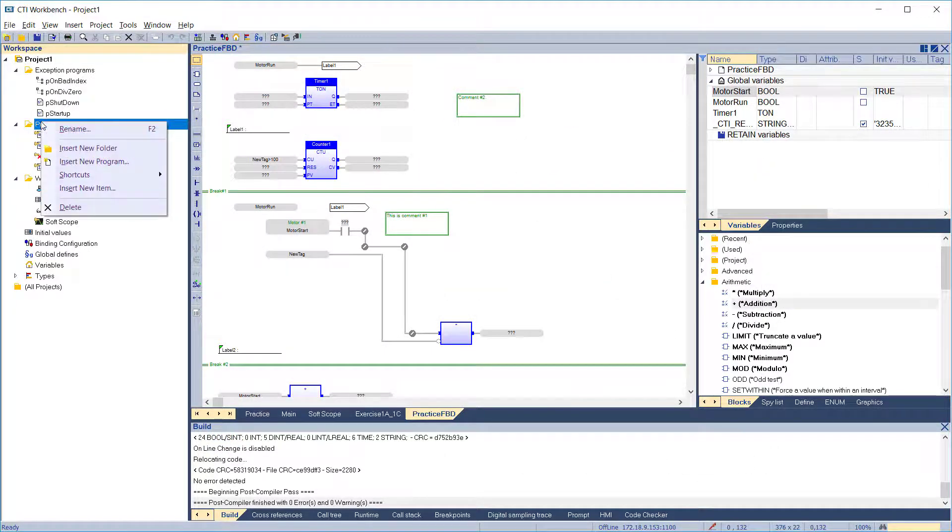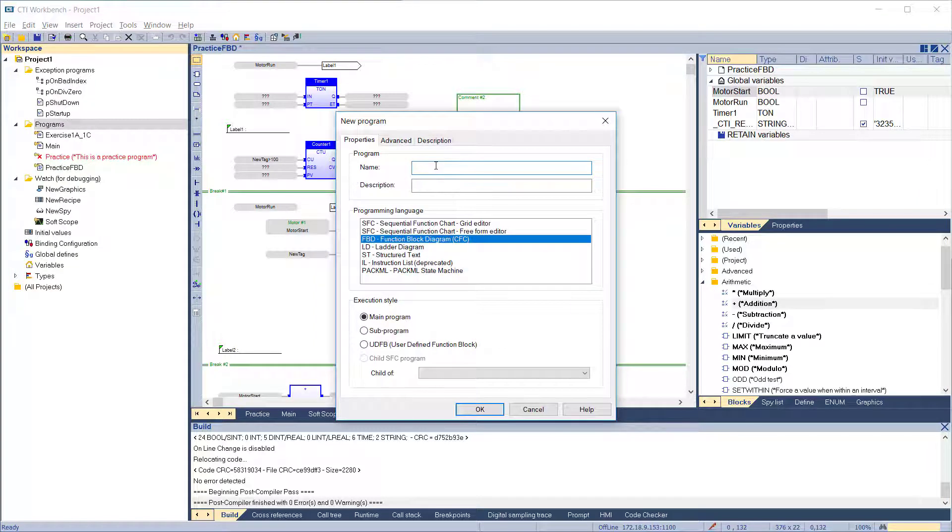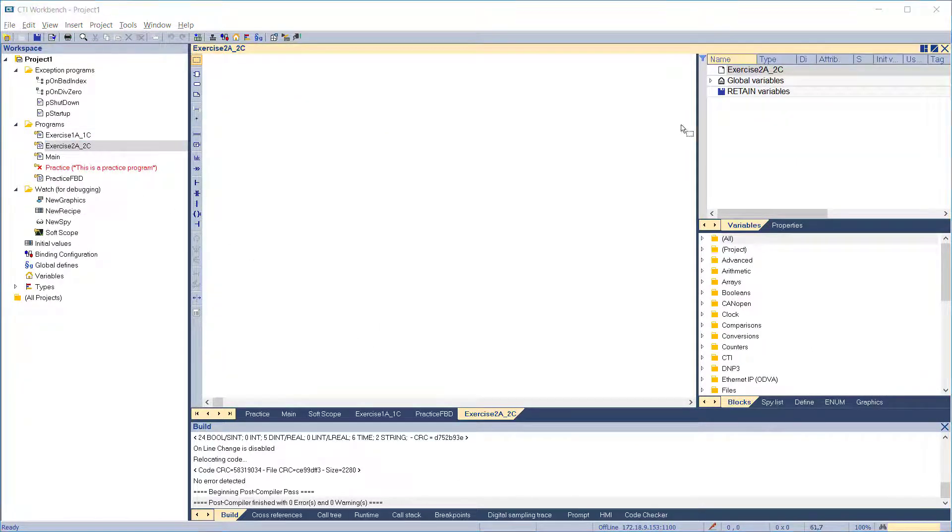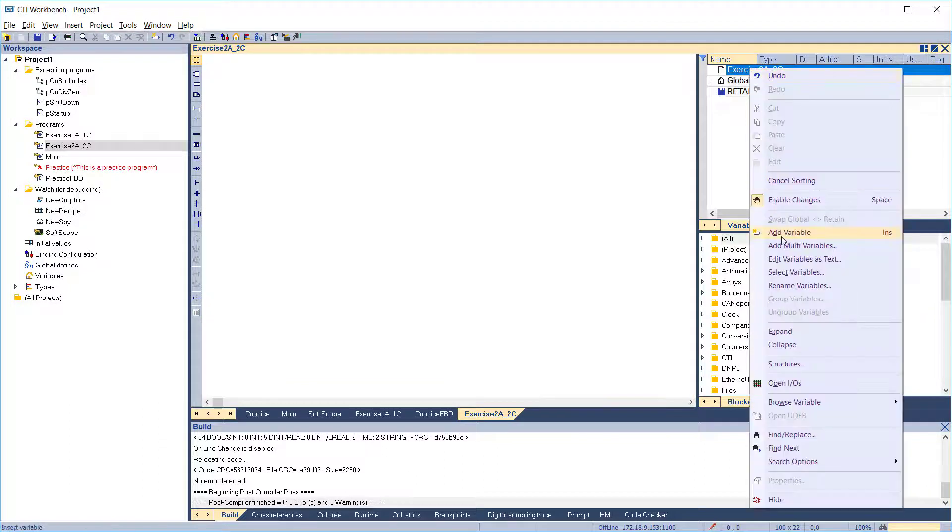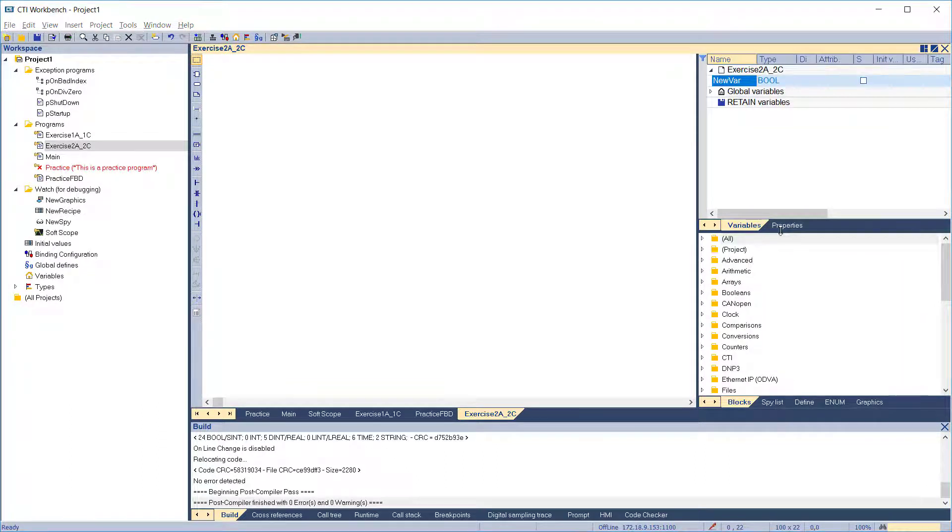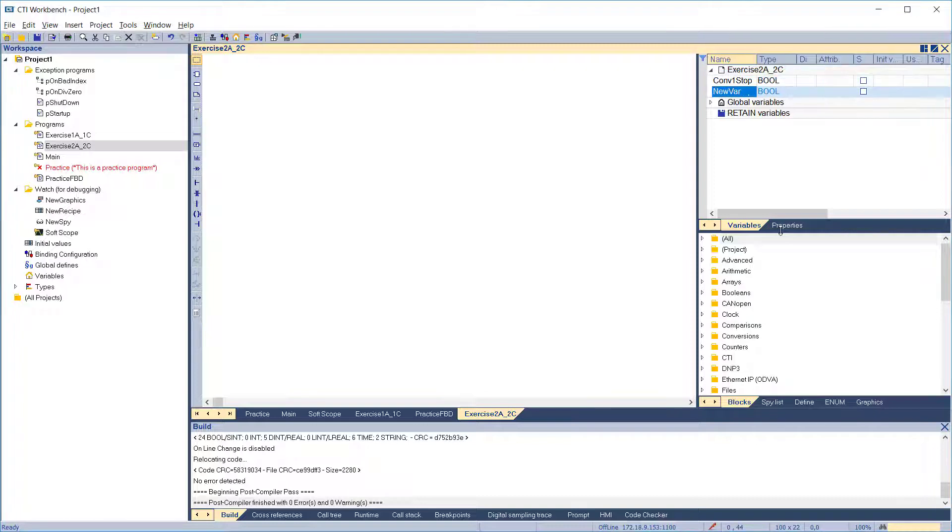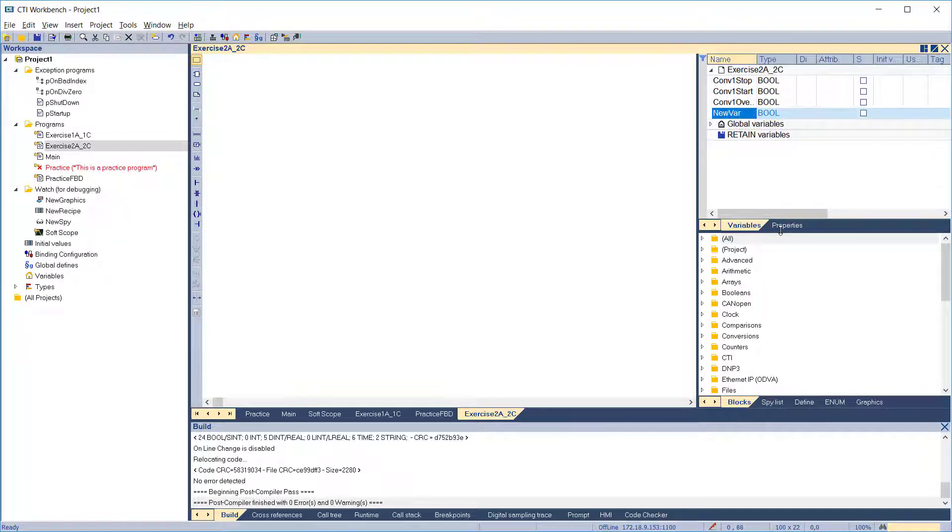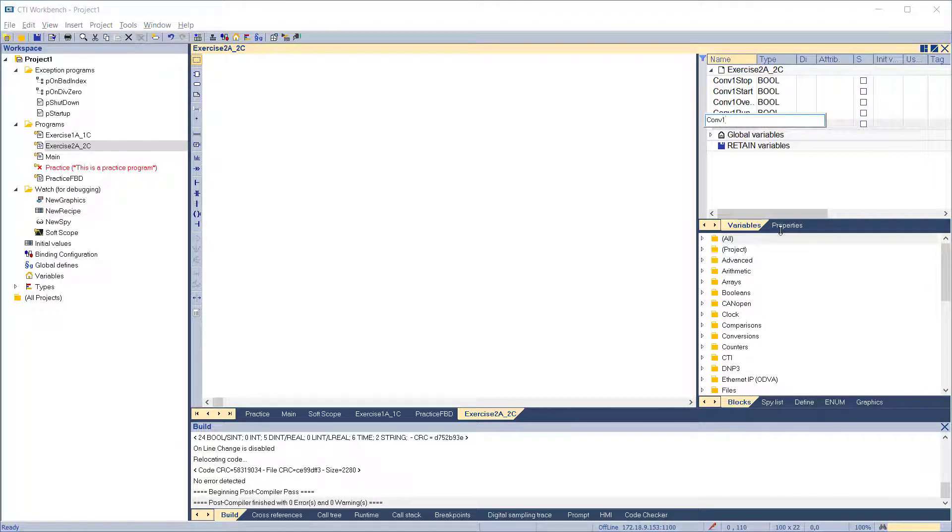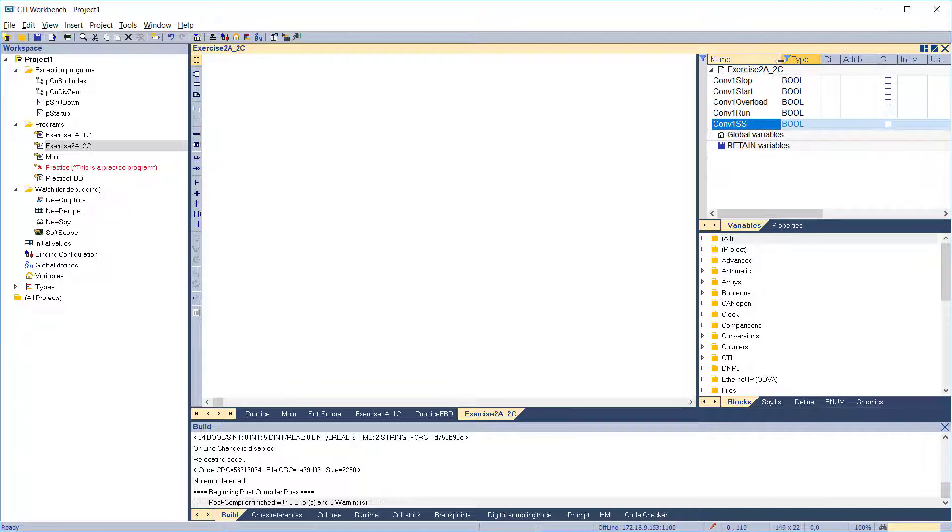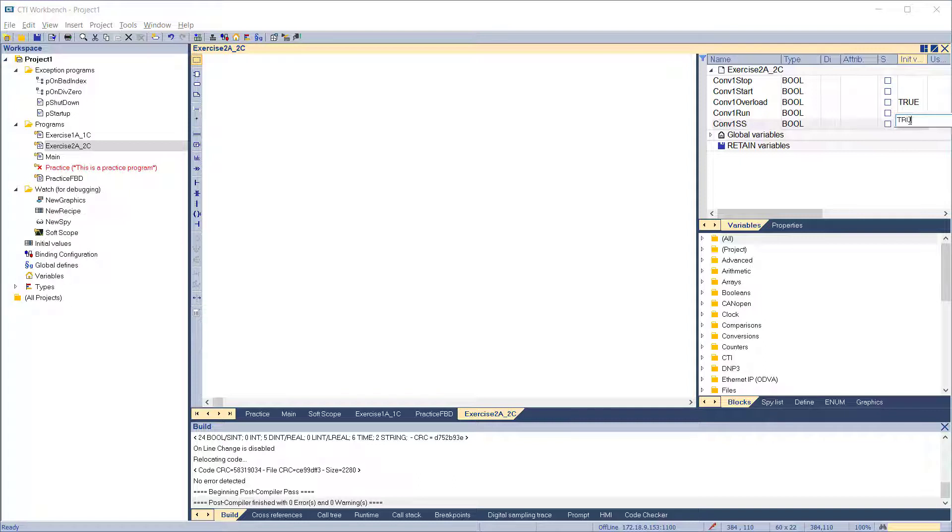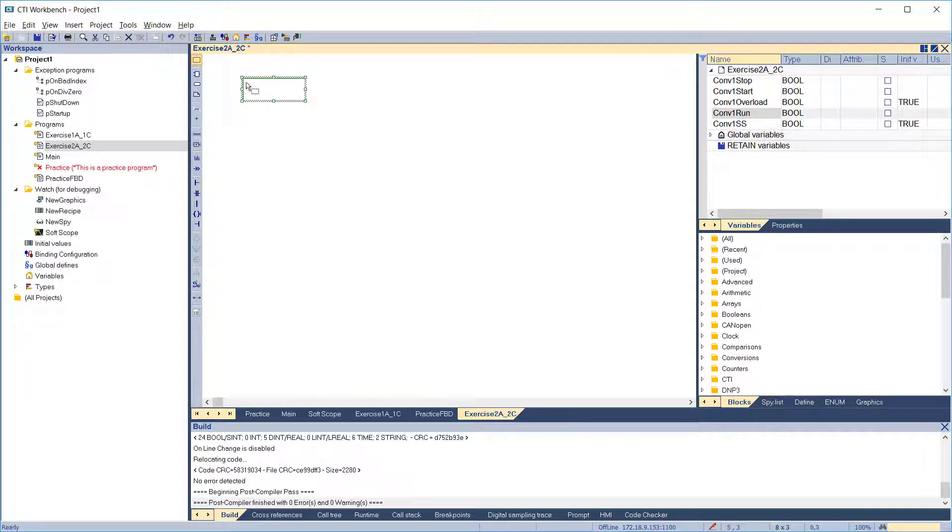We'll start by adding a new program. Call it exercise 2a, programmed in FBD. Then open it for editing. Next, we'll create all the needed variables: conveyor 1 stop, conveyor 1 start, conveyor 1 overload, conveyor 1 run, conveyor 1 safety stop. All are booleans. We need to set an initial condition of true for the overload and safety stop variables since they are normally closed. This would not be necessary in a real system because the IO scan would set these values for us when the program starts. We'll start with a comment so we know what the program is for.